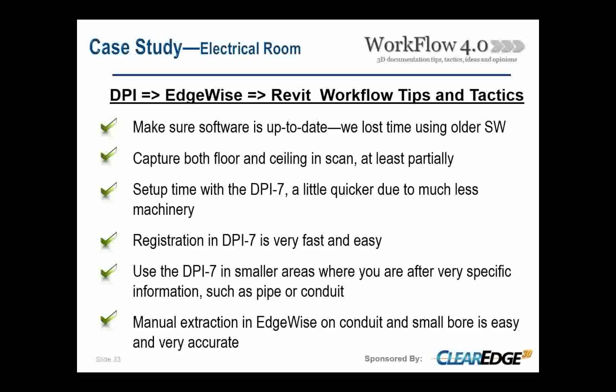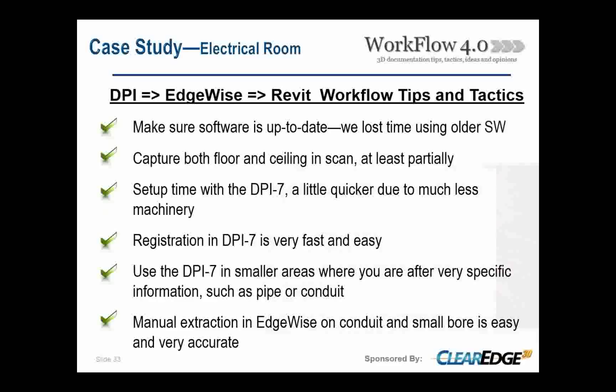Because of the small size of the conduits we were trying to pull out, manual extraction ended up being more accurate for us. For the larger pipes and ductwork, the automatic extraction would have been better. The DPI-7 does not like planar surfaces, so we had to place targets along vertical walls and flat surfaces to maintain tracking and keep everything together, providing good differential between areas so the scanner could track the scan more reliably.